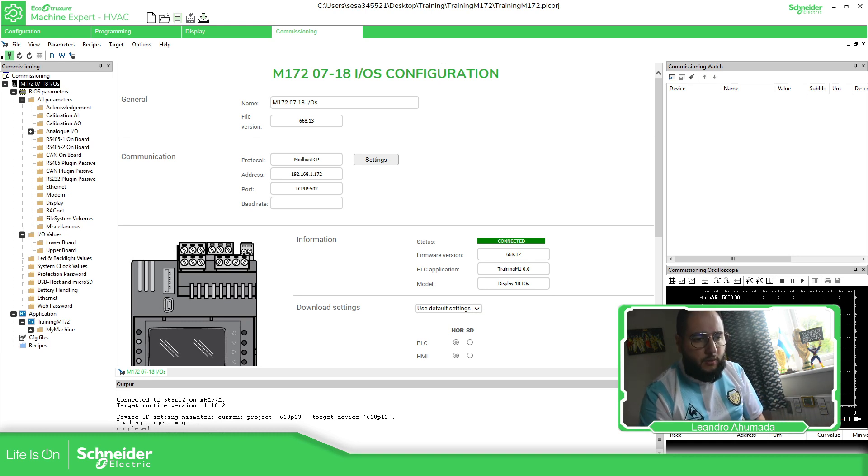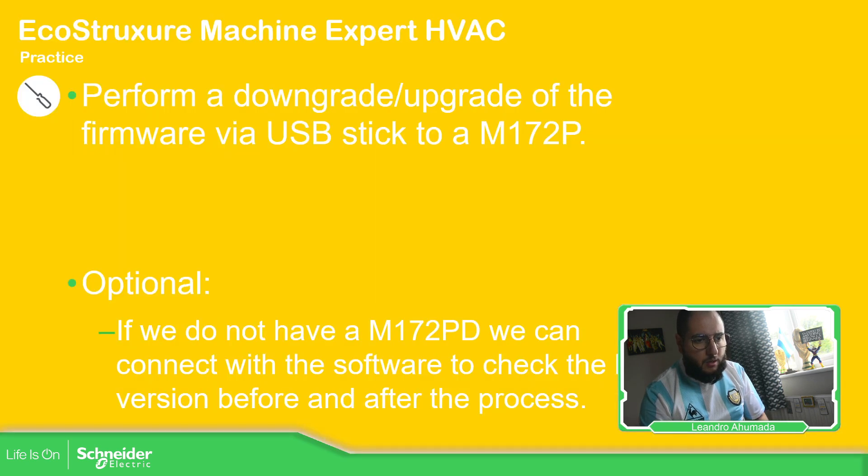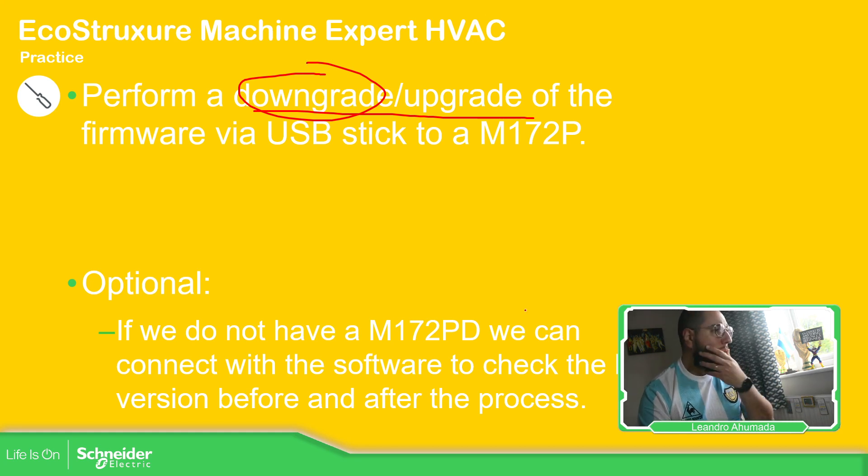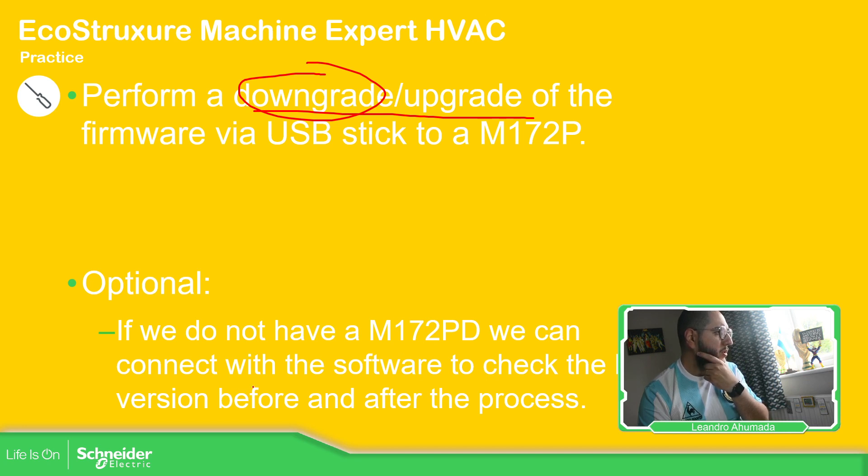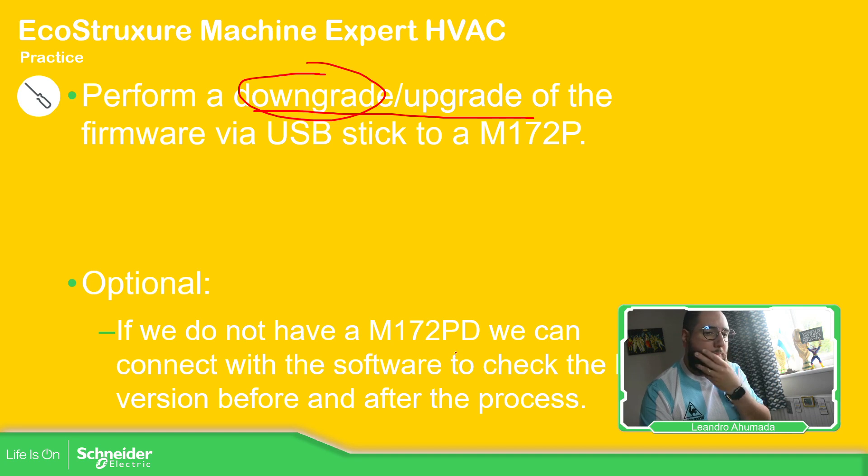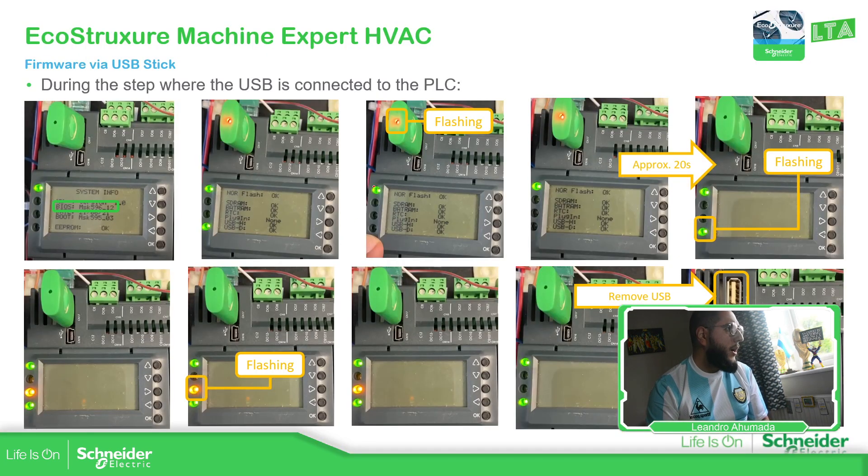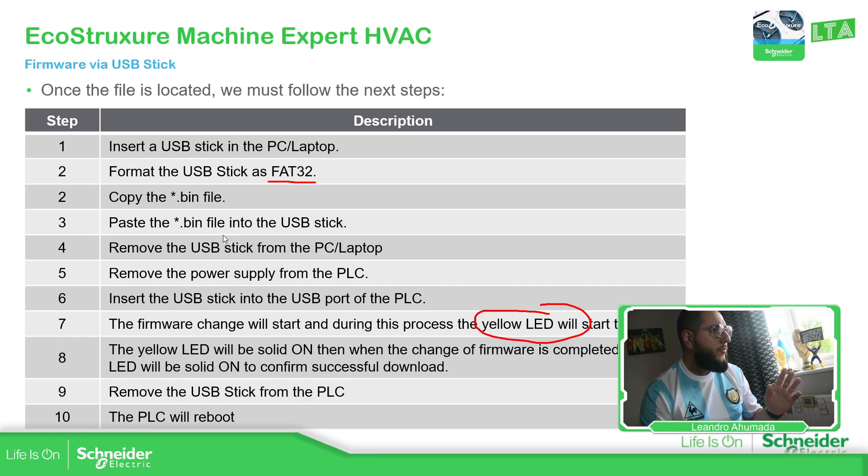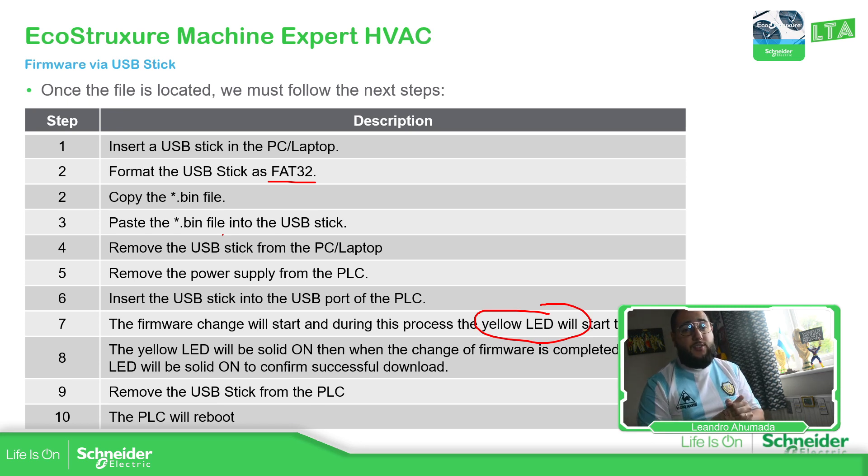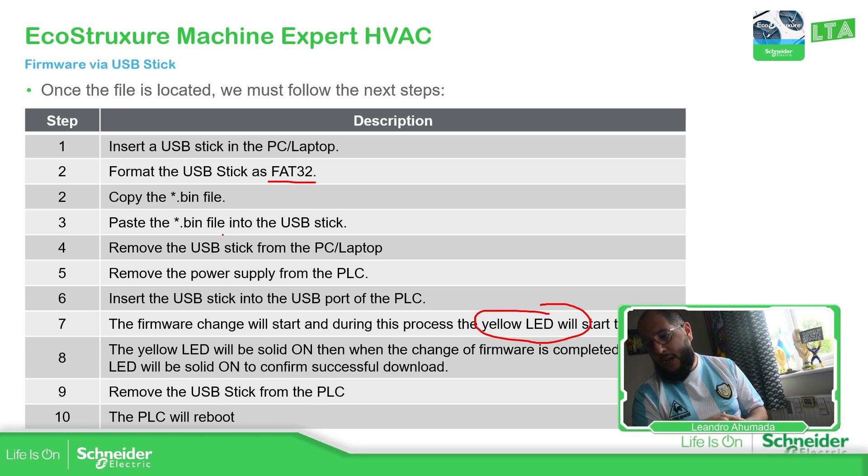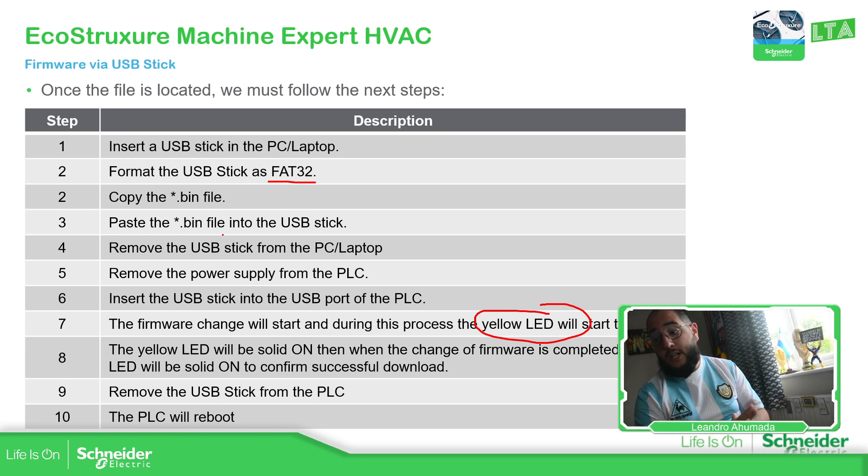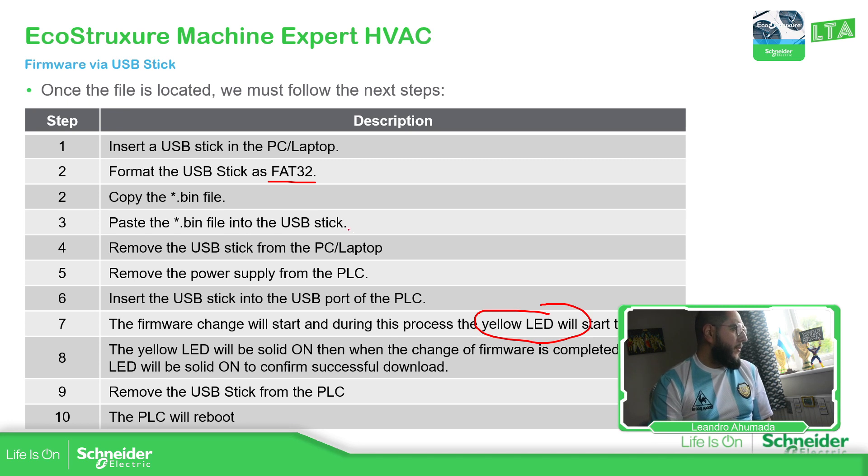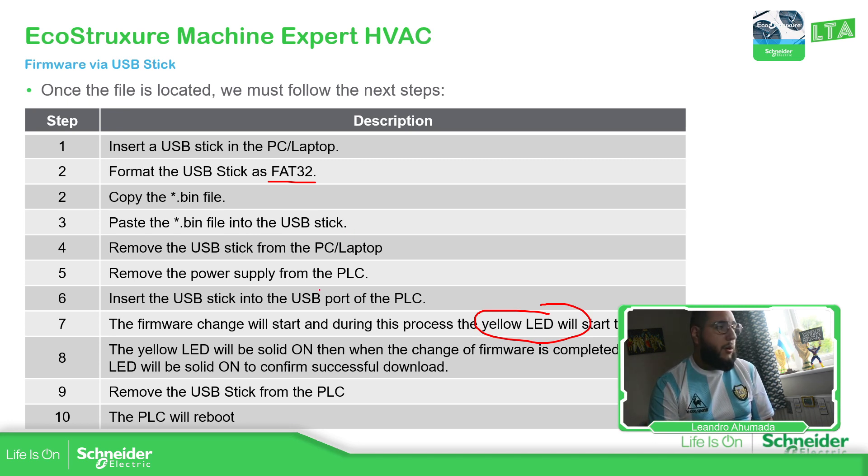This is how you can change the firmware of the controller. So let's perform this downgrade or upgrade. In my case it was downgrade, but the upgrade is going to be the same. Optionally, we can connect with the software to check the BIOS version before and after. This is what we have done. This is what we have done in order to check the version of the firmware. But basically, this is the process, the steps. Remember to format the USB stick in FAT32. I don't remember if there's a limitation of the size. I think that would be in the hardware manual equipment, but in my case I'm using one of eight gigs. I usually don't use anything more than 16 or 32 gigs.